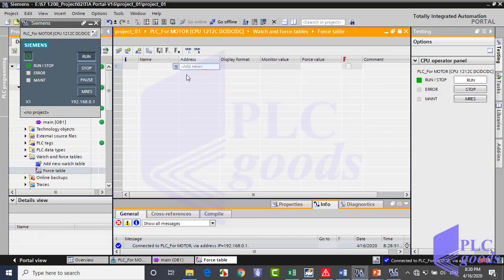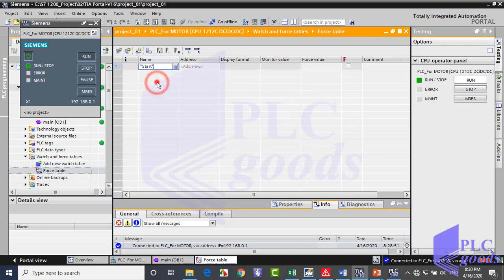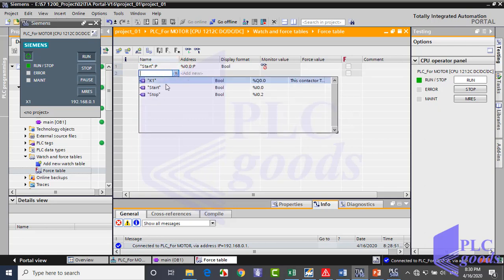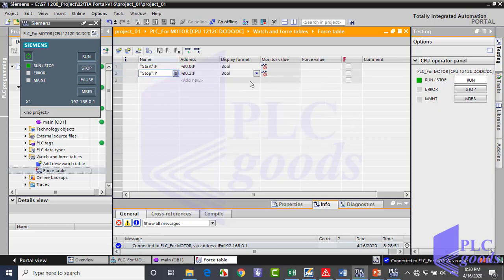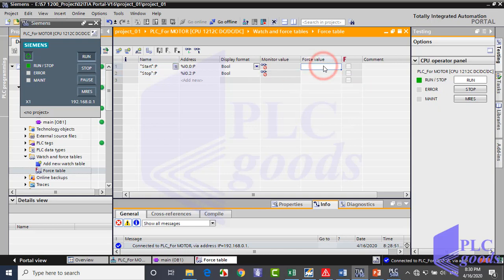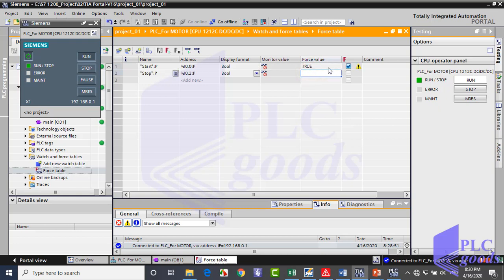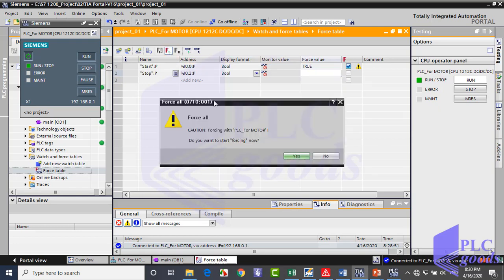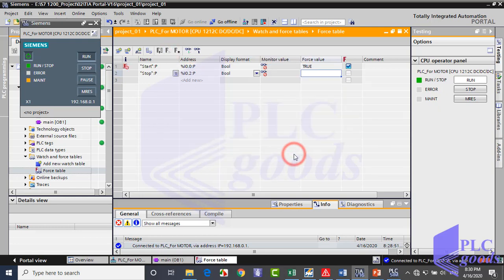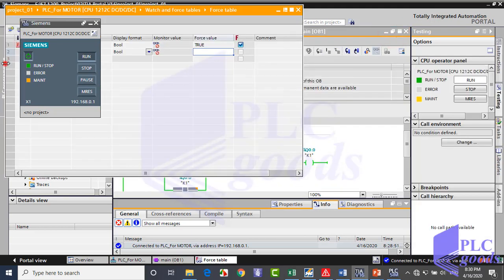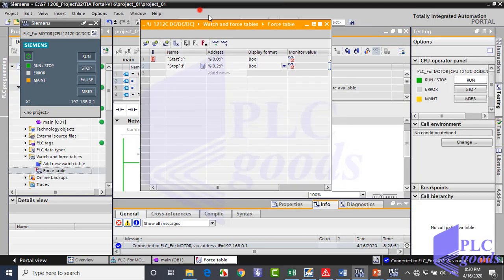First select any input address which you want to change. I select my start tag with I0.0 address and also stop tag with I0.2 address. And here write a valid value. For a binary address like I0.0, we just have two valid values: 0 or 1, in other words false or true. I write 1 here. Then click on this icon to use the inserted value in the program instead of the real value. As you see, the MAINT LED color is changed to orange because this way is usually used in maintenance processes.